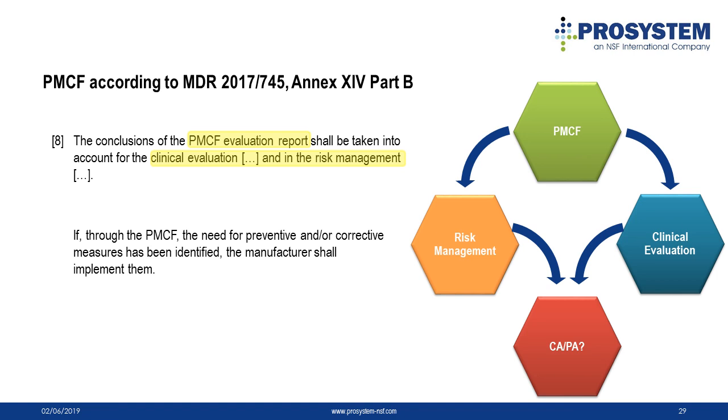The manufacturer shall analyze the findings of the PMCF and document the results in a PMCF evaluation report that shall be part of the clinical evaluation report and the technical documentation. The conclusion of the PMCF evaluation report shall be taken into account for the clinical evaluation and in the risk management. If through the PMCF the need for preventive or corrective measures has been identified, the manufacturer shall implement them.